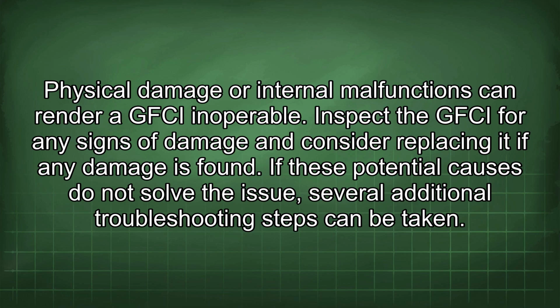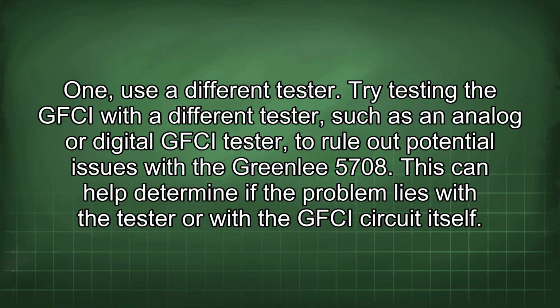If these potential causes do not solve the issue, several additional troubleshooting steps can be taken. 1. Use a different tester. Try testing the GFCI with a different tester, such as an analog or digital GFCI tester, to rule out potential issues with the Greenlee 5708. This can help determine if the problem lies with the tester or with the GFCI circuit itself.